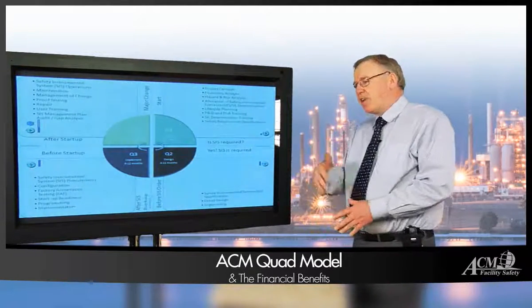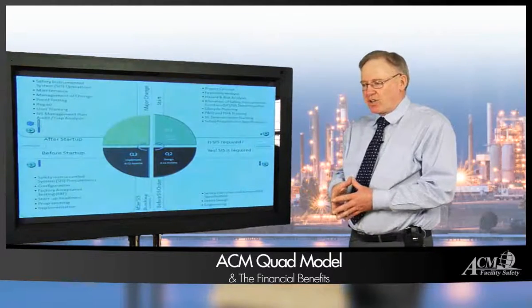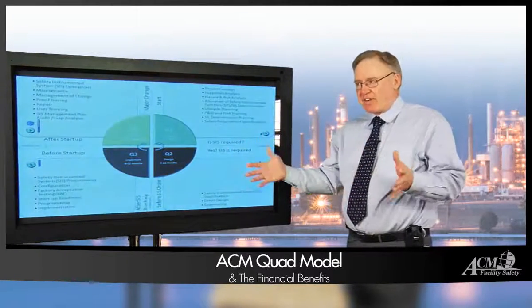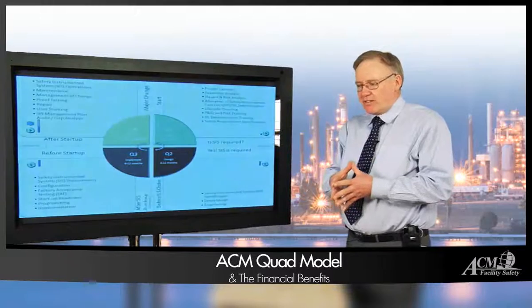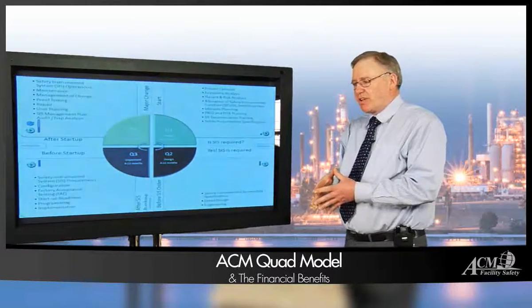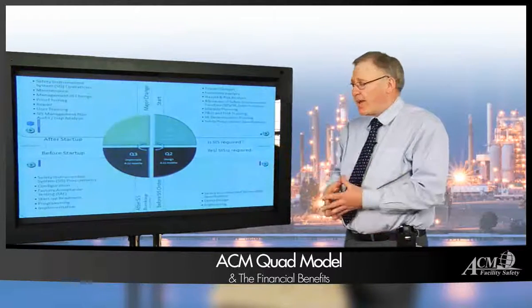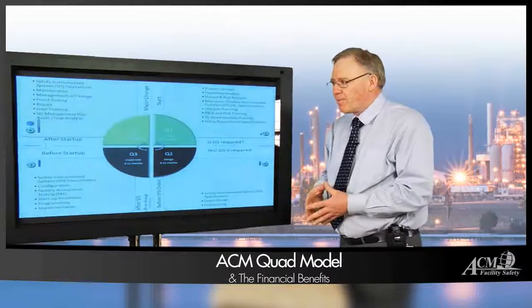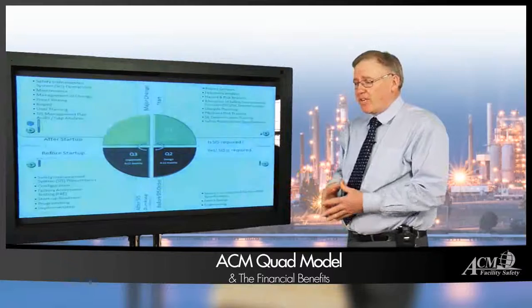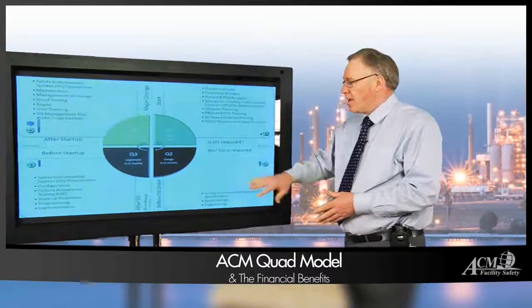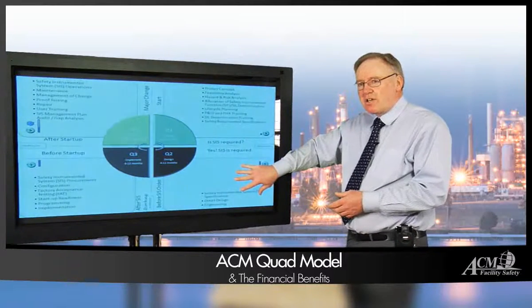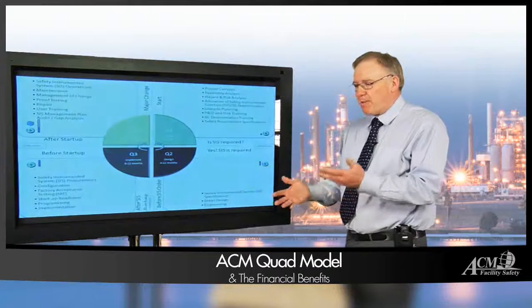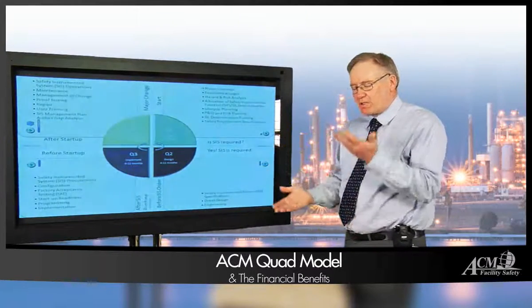Or going the other way, you can actually extend the testing frequency. In other words, instead of 2 years or 3 years, you can extend it to maybe 5 years and put in a little more hardware so you can actually survive a failure. So that's fantastic. Now you're adding in more capital costs, but you're reducing the operational cost. So Q2 is a real balance between CapEx and OpEx cost.